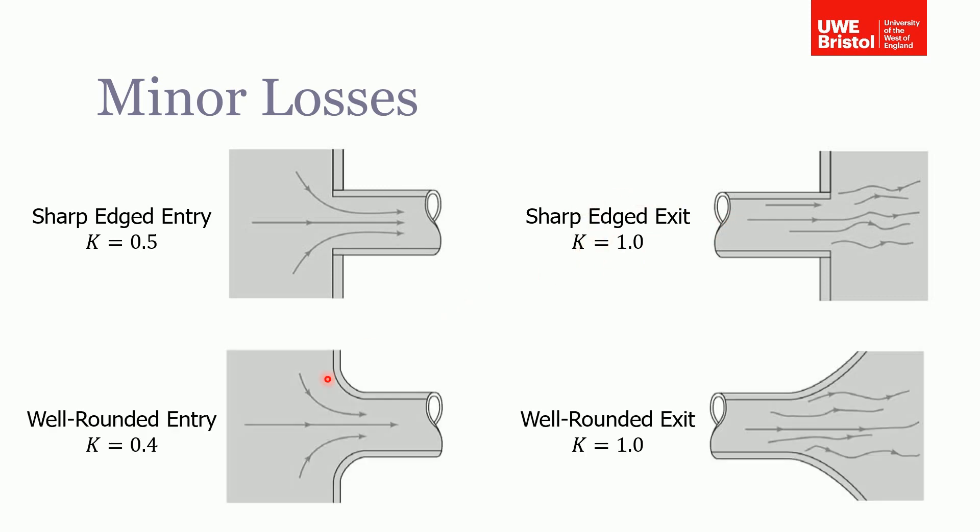You can see it changes slightly for a well-rounded entry—it's slightly reduced to 0.4, which means it's going to have a smaller pressure loss, but you see it makes no difference on the exit.